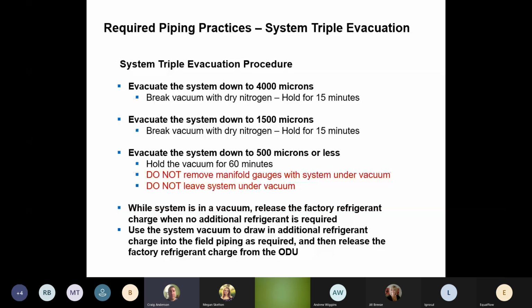When we're talking about bringing it under the 500 microns, we want to bring it under the 500 microns and we want to hold it there. Not bring it to 500 microns, turn your gauges off, turn everything off and crack the lines and let's go. Let's isolate your gauges, isolate the vacuum. Let's hold it under 500 microns.